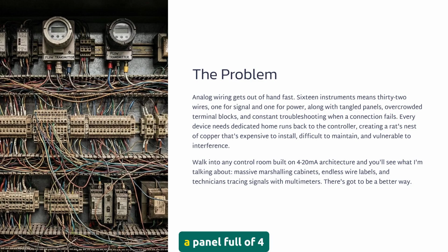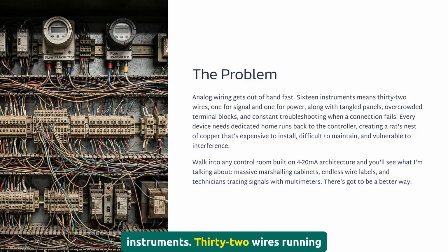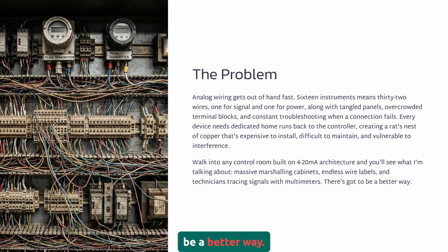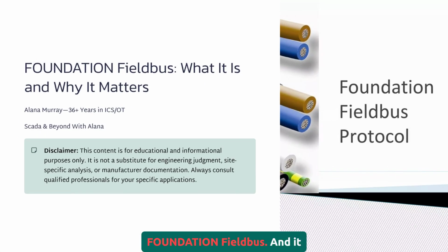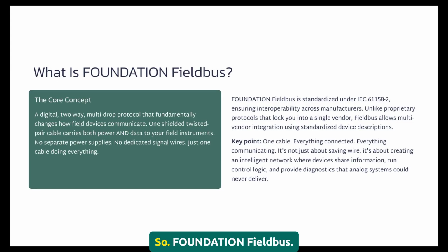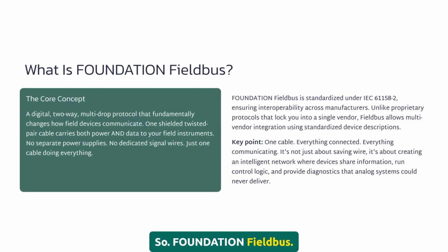You're standing in front of a panel full of 4 to 20 milliamp wiring that looks like a spaghetti bowl. 16 instruments, 32 wires running everywhere. One's already failing. You're thinking there's gotta be a better way. Well, there is. That's Foundation Fieldbus. And it changes everything about how you wire, think about, and control your field devices. Let's dig in.